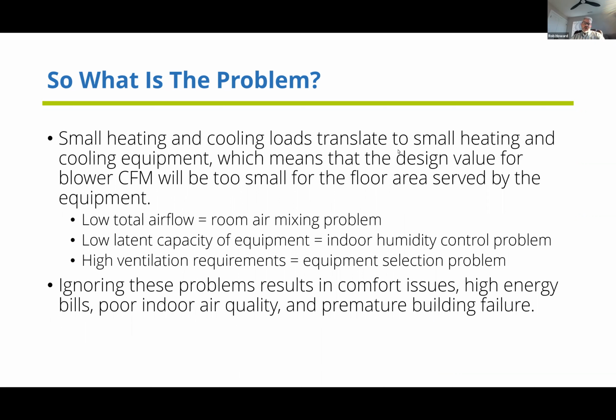So what's the problem? Small heating and cooling loads translate to equipment with lower CFM available to mix the air in the home. So while you don't need a lot of BTUs generated, you do need sufficient airflow to move those BTUs around the house to keep it consistently comfortable. What we end up with is a room air mixing problem.